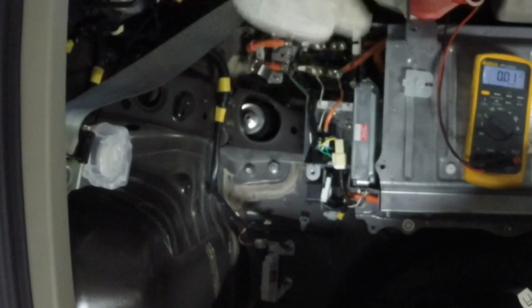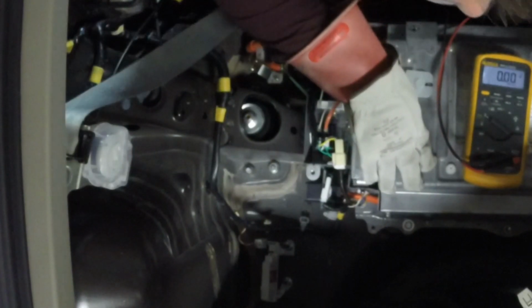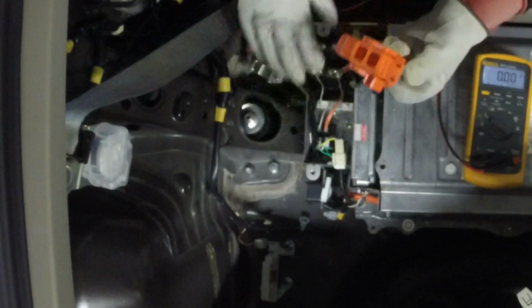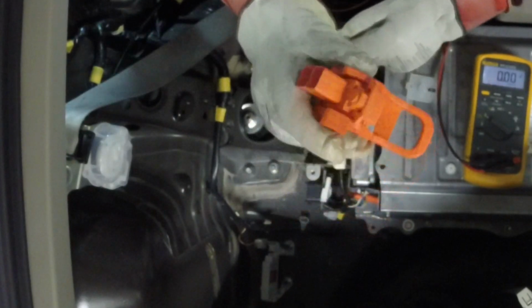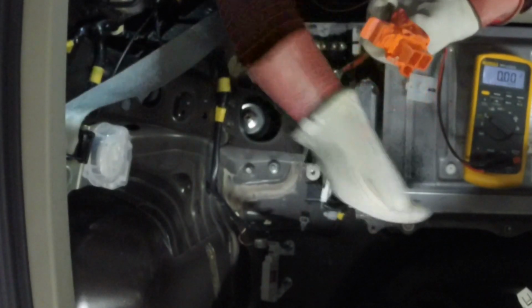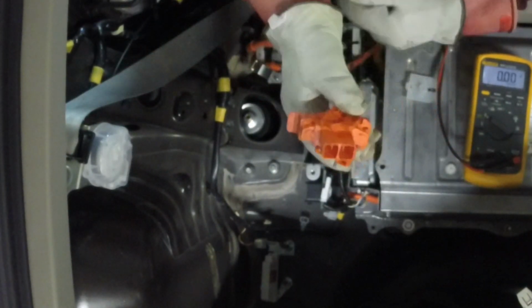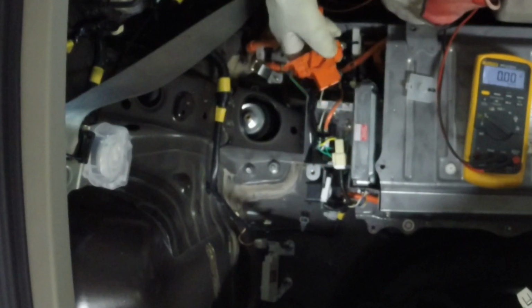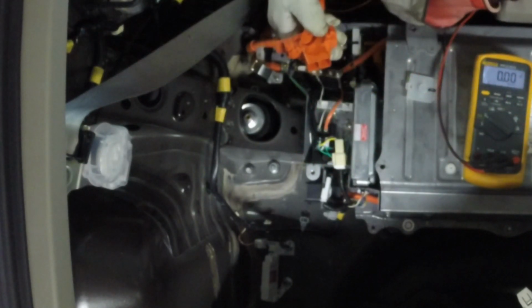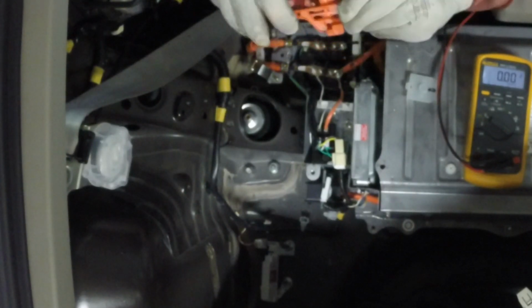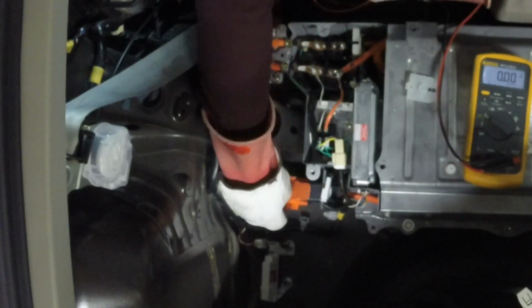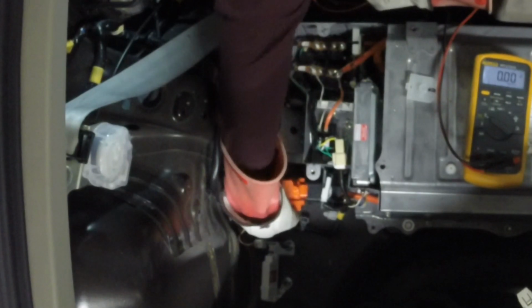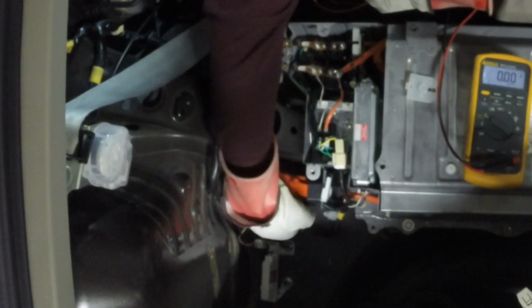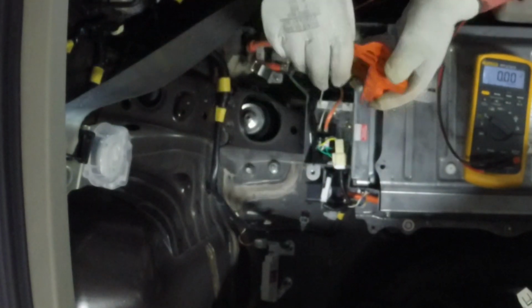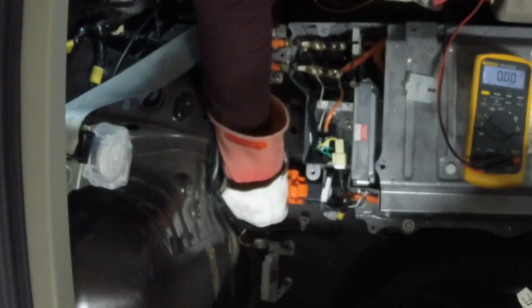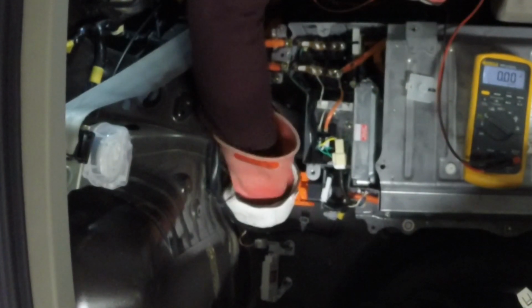Because we disconnected our high voltage service plug. So even if we got to the point where we had open terminals over here, because this is disconnected, it disconnects the pack about halfway through. So there's 0 volts between these two terminals because there's no continuity through the rest of the pack. If I were to plug this back in—helps if you go the right way in—go down here. There we go.